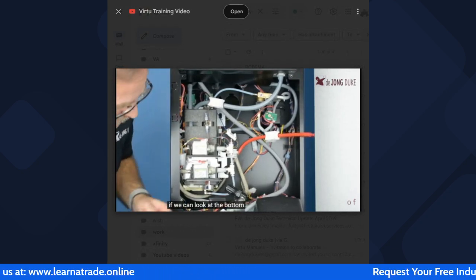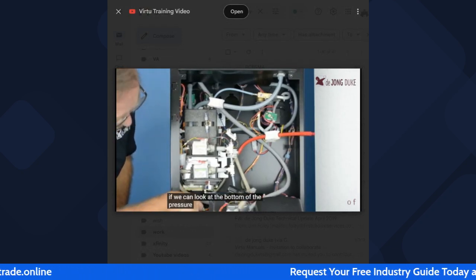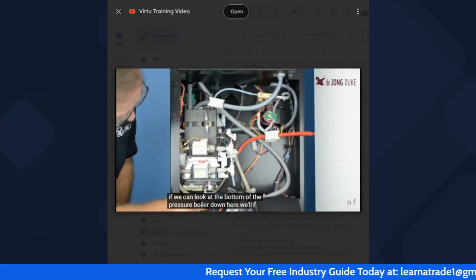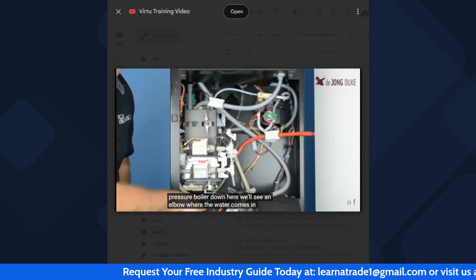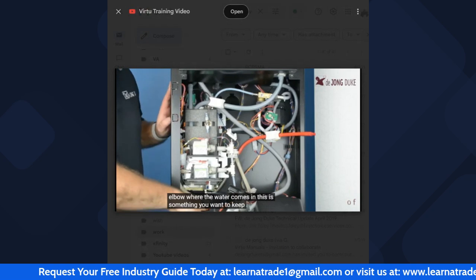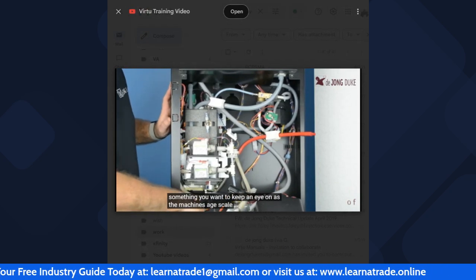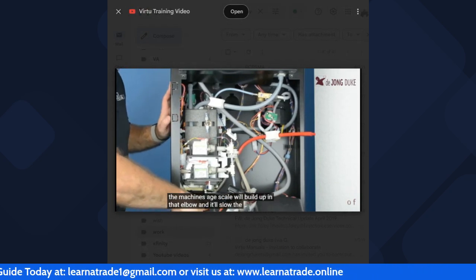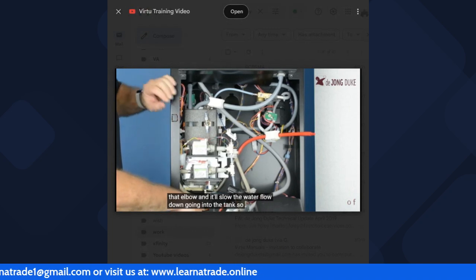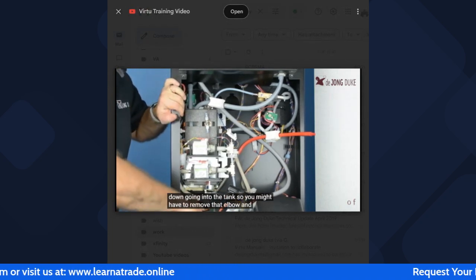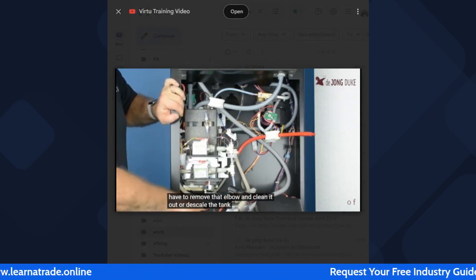If we look at the bottom of the pressure boiler down here, we'll see an elbow where the water comes in. This is something you want to keep an eye on. As the machines age, scale will build up in that elbow and slow the water flow going into the tank. So you might have to remove that elbow and clean it out, or descale the tank.